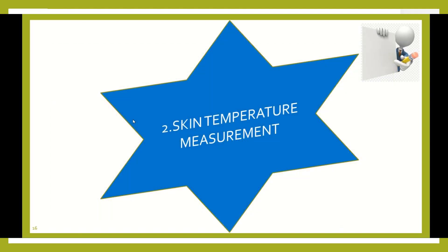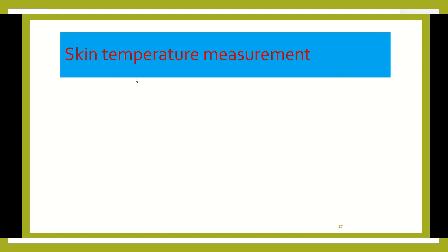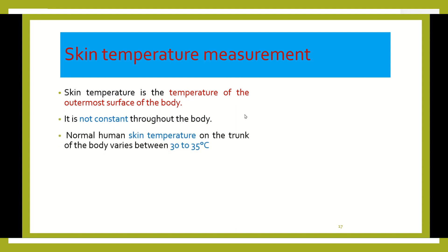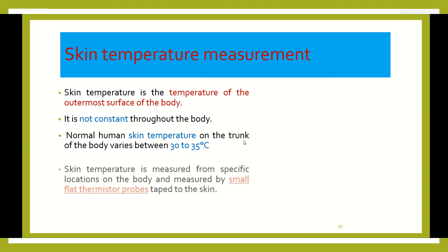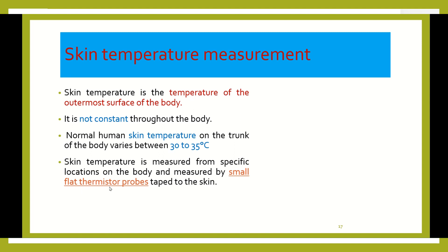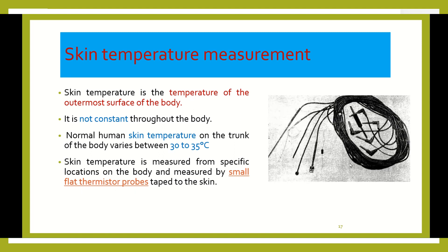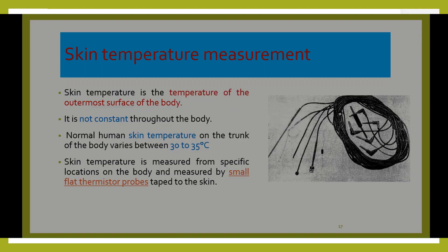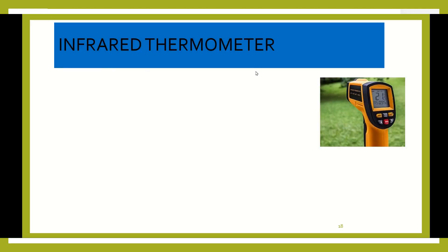We have now discussed systemic body temperature measurement and the devices used. Let us move to skin temperature measurement. Skin temperature arises from the skin surface and is also called surface temperature. It is not constant throughout the body; normally, skin temperature varies from 30 to 35 degrees centigrade. To measure skin temperature, we can use small flat thermistor probes.